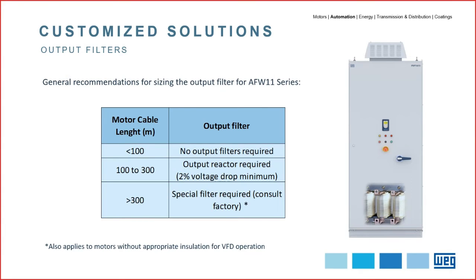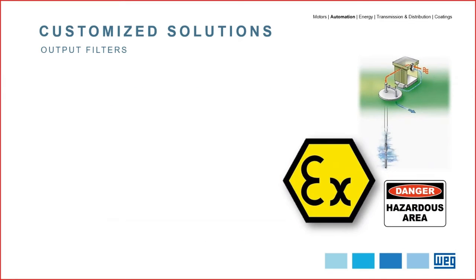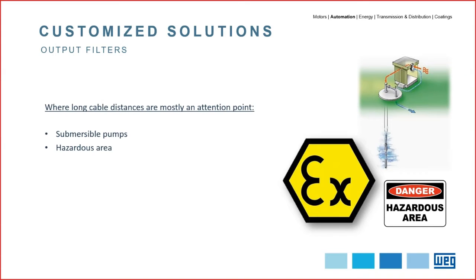The usage of special filters is also recommended for motors without an appropriate insulation system to be controlled by a VSD. For example, when you already have the motor and don't want to replace it, but you are moving to a VSD starting method. So long cable distances are always an attention point in specific applications, for example, where you have a submersible pump installed, and where there are VSDs installed in hazardous areas, which normally demands long cable distances between the VSD and the motor.